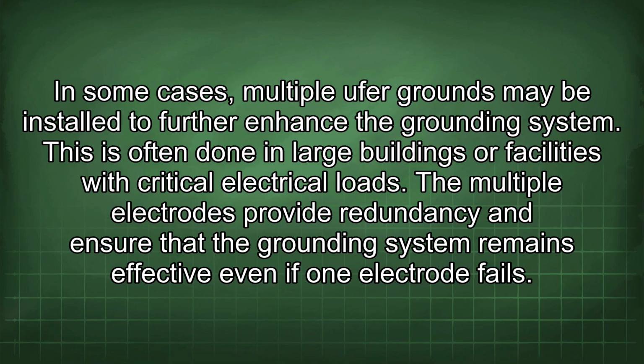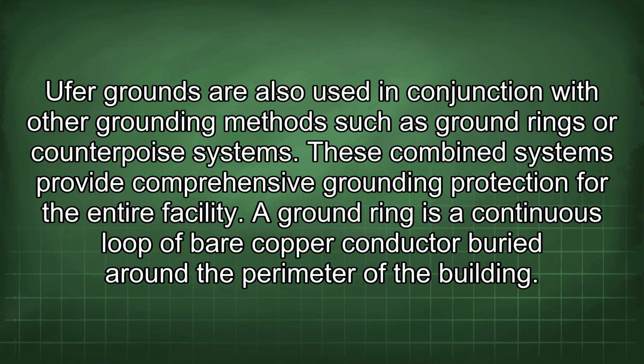In some cases, multiple Ufer grounds may be installed to further enhance the grounding system. This is often done in large buildings or facilities with critical electrical loads. The multiple electrodes provide redundancy and ensure that the grounding system remains effective even if one electrode fails. Ufer grounds are also used in conjunction with other grounding methods such as ground rings or counterpoise systems. These combined systems provide comprehensive grounding protection for the entire facility.